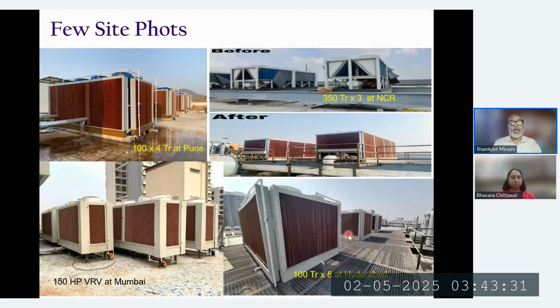So how do we cool it down? The answer is we encapsulate the complete chiller with cooling media. We allow water to trickle on the cooling media, and air travels through this media, offering cold air to the condenser, bringing the condenser back to its design condition.